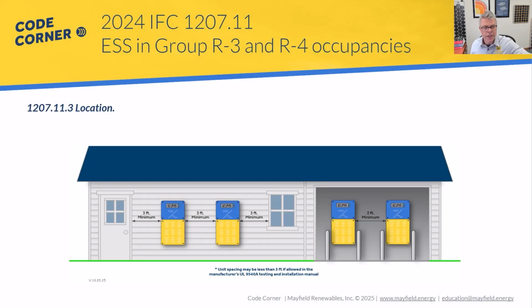So the image here that I wanted to show you, we use this image a fair amount, but in residential applications, what I want to focus in on is those units that are installed on the outside, where we have a 3-foot minimum separation from windows and doors that are directly entering that dwelling unit. The 3-foot separation between the units, we've talked about that in other videos on size and separation. But for this one, I just wanted to help illustrate where that 3 feet would be for those units that are directly entering the dwelling units.